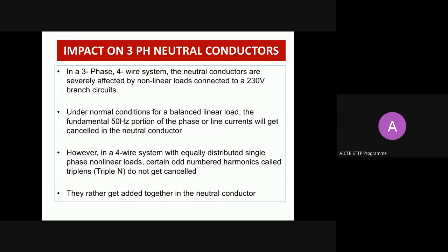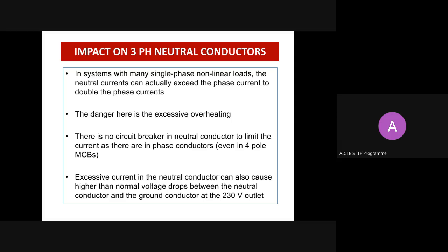Next to transformer heating, the important element is the neutral conductor. Because of unbalance and non-linear loads, the neutral conductor current increases. Normally, in a balanced load, the neutral current gets cancelled because of the balanced linear current, and there will be no harmonic current in the neutral conductor. But with more non-linear loads, the neutral conductor current will be higher than the phase current. That leads to damage of the neutral conductor. The danger is excessive overheating of the neutral conductor.